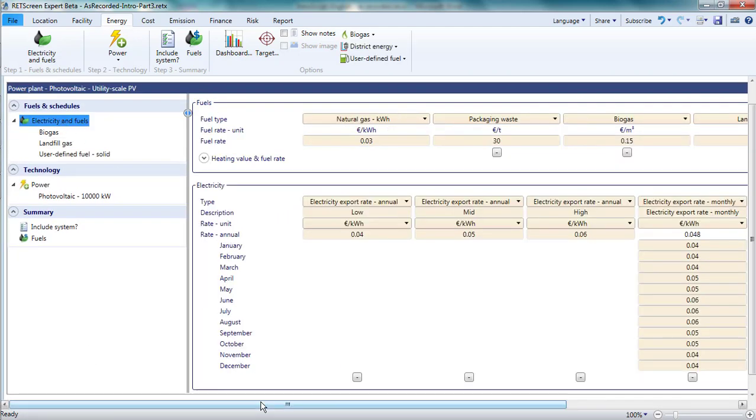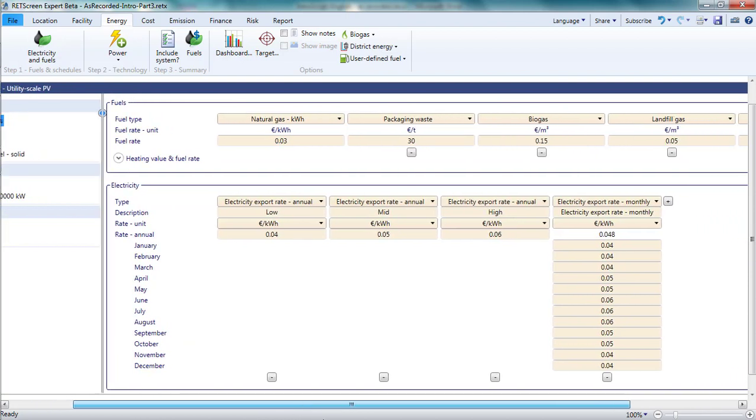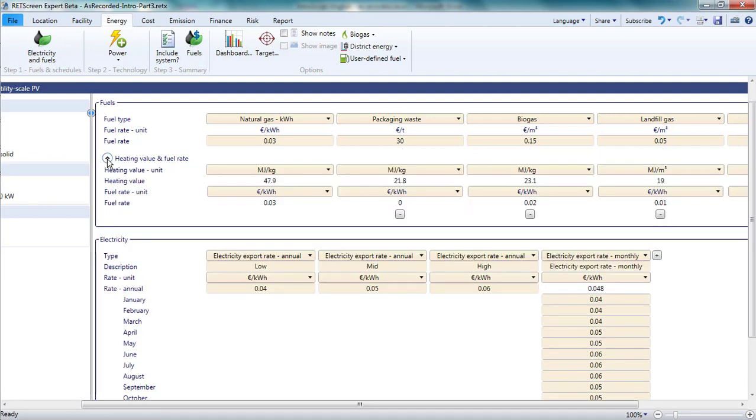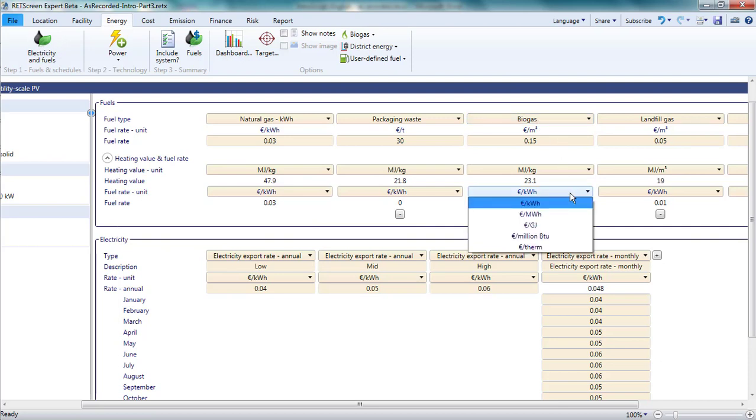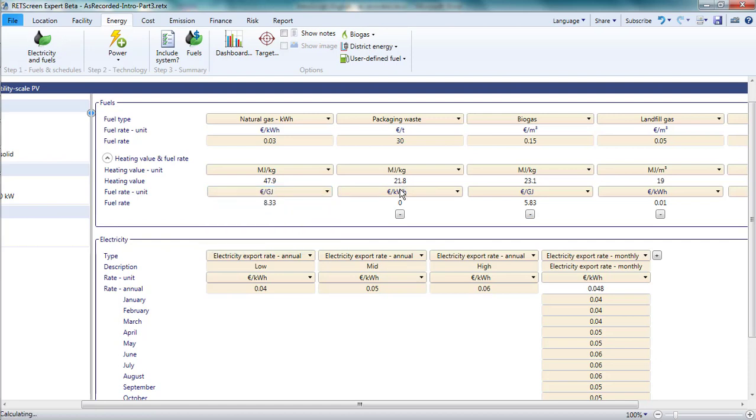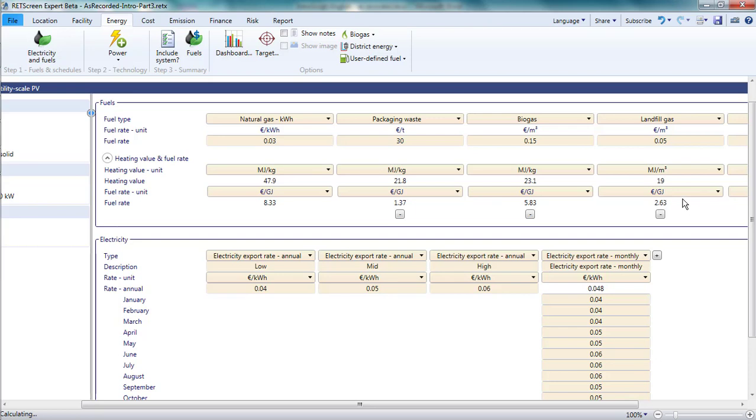Note that there is a down arrow icon beside the text heating value and fuel rate at the bottom of the fuels box. Clicking on this shows the heating value and fuel rate in units of my choice. This is useful in two ways. First, if I have a fuel in one unit, but I want to know what the fuel rate would be in another unit, RETScreen will do the conversion here. Second, I can compare the energy content and cost per unit of energy across fuels using the same units. In this case, megajoules per kilogram and euros per gigajoule of energy.